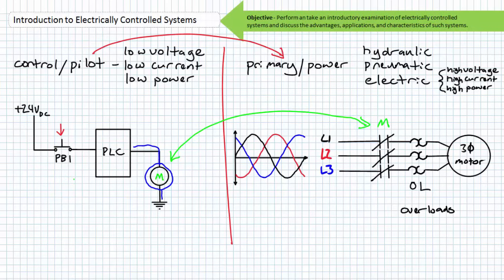As self-evident and clear as the distinction and separation of pilot and primary is in an electrically controlled hydraulic system, so too must be the distinction and separation of pilot and primary in an electrically controlled motor system. The pilot signal is low voltage, low current, low power electricity, entirely separate and electrically isolated from the high voltage, high current, high power primary input, and must always remain so. The only interaction between the pilot and primary electrical signal is via magnetic or mechanical means. They are electrically isolated for a reason, and the primary reason is safety.